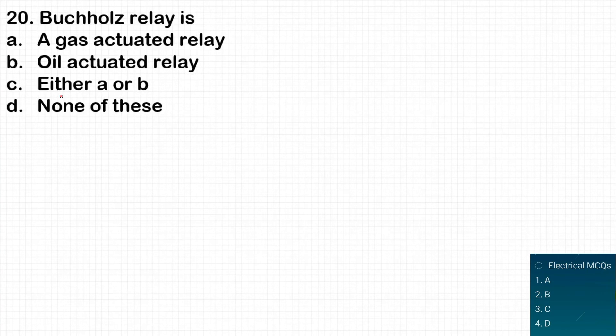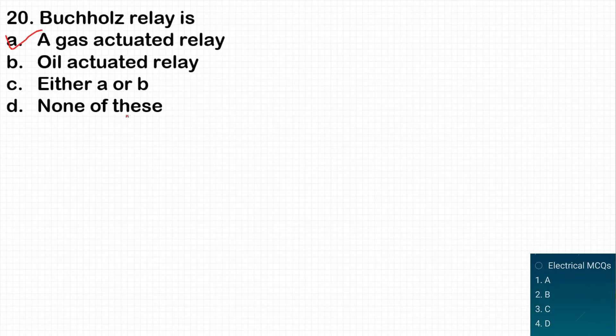The next question: the Buchholz relay is a gas-actuated relay, an oil-actuated relay, either, or none? The Buchholz relay is a gas-actuated relay. It operates when, due to some fault in an oil-immersed transformer, gas is produced, and the relay actuates based on that gas production.